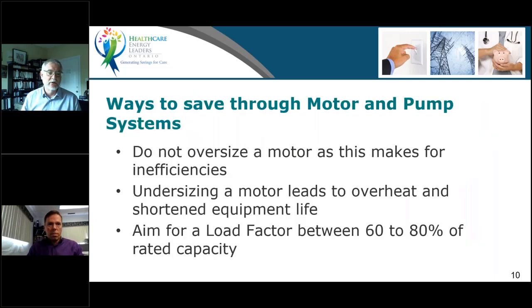So don't oversize the motor, because that makes for inefficiency. Don't oversize the pump, and typically that's what you end up with, an oversized pump and motor. Undersizing can definitely lead to shortening of life, but that's where having things like speed control can help you, because you can deal with a high requirement and a low requirement within the same system, and not strain it either way, either overloading it or oversizing it. And typically you want to work within that 60 to 80% loading on the motor.